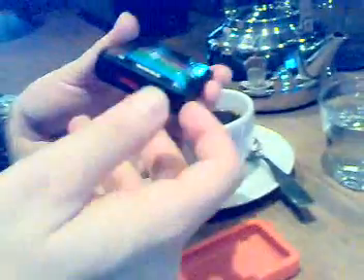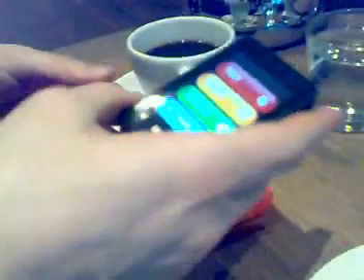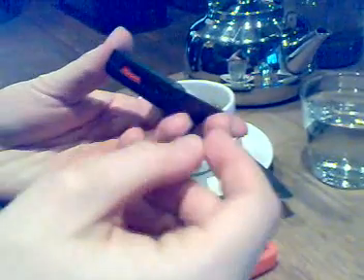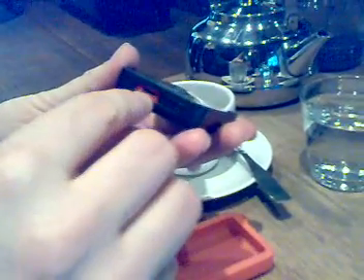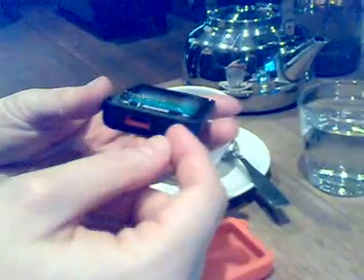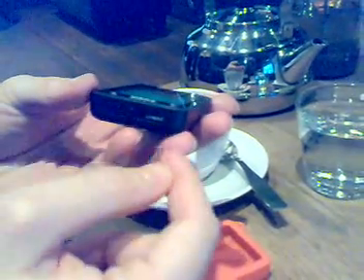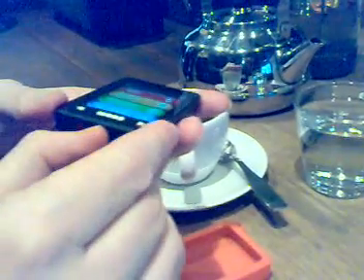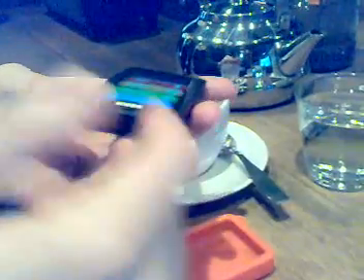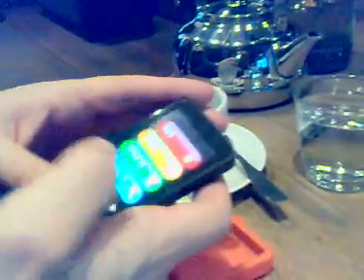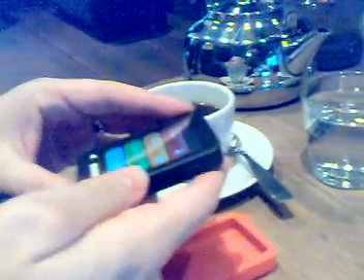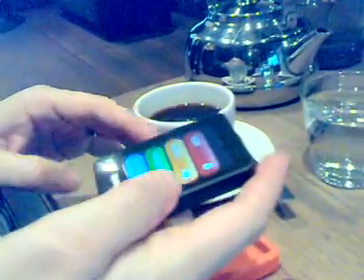So the user still needs to use the device and prick the finger to get the blood sample. He or she inserts the test strip into the measurement module. The measurement module is actually protected, and it's made so that you cannot charge the device and measure at the same time, because that would be dangerous. We have patented this one as well. In total we now have nine different patents for the technology for the user.